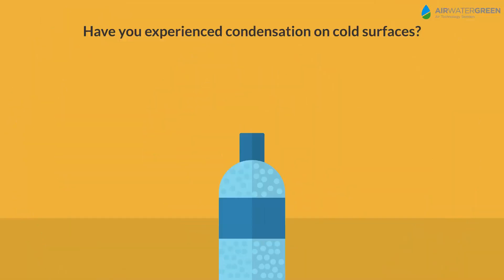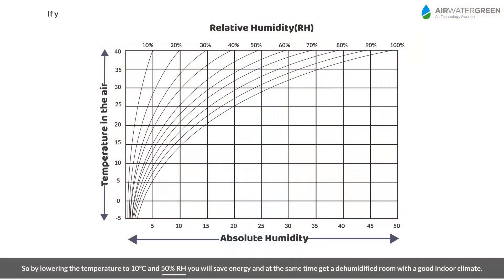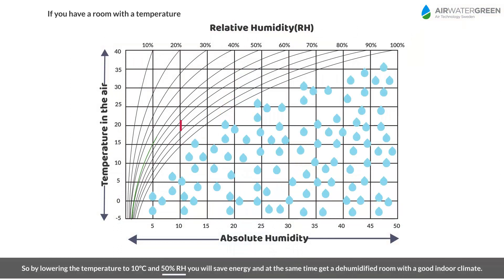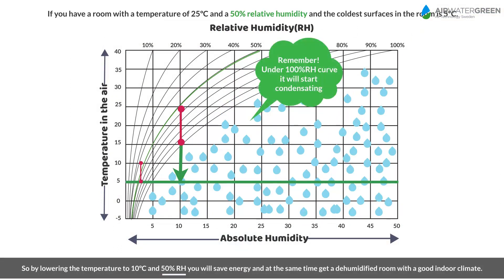Have you experienced condensation on cold surfaces? If you have a room with 25 degrees Celsius and 50% relative humidity, and the coldest surface in the room is 5 degrees Celsius, remember that below the 100% relative humidity curve it will start condensating.